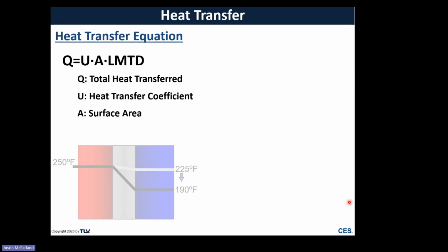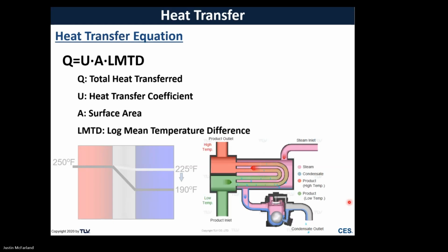We have the surface area, A, and then the log mean temperature difference. So LMTD, you can kind of simplify that down to, if you can imagine the difference between the process temperature coming in and the process temperature coming out. It's not exactly what it is. It's a little bit more of a complex formula, but it's more or less a way to compare the different temperatures of the hot side and the cold side process streams, just to get an accurate temperature difference of everything that's going on.